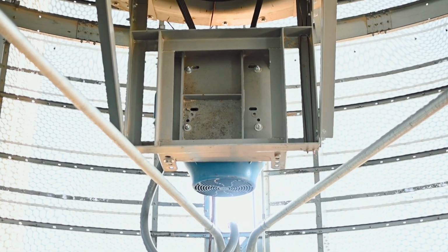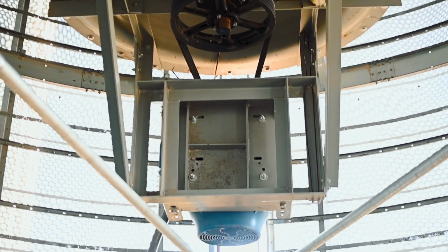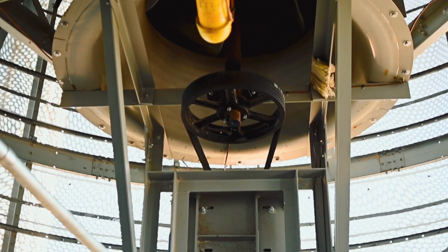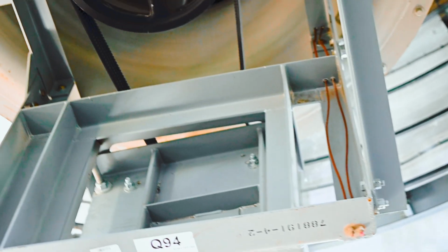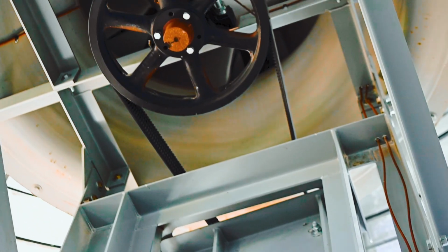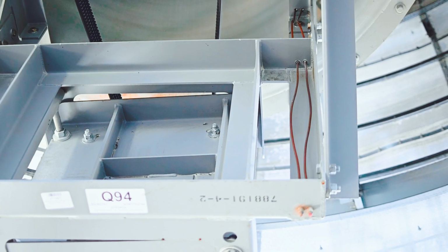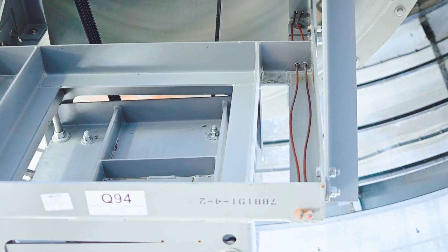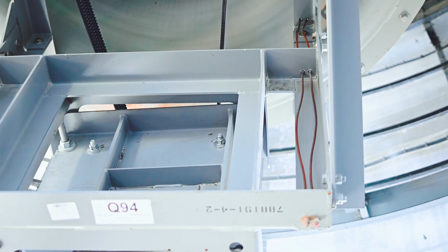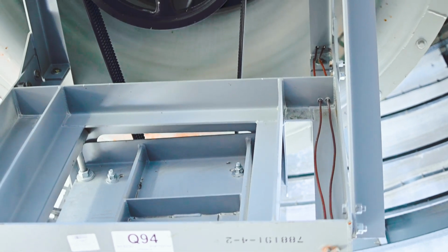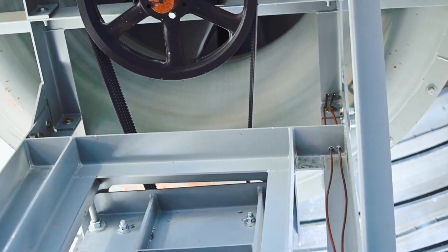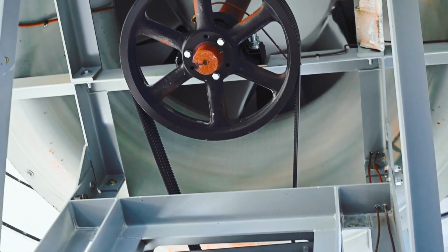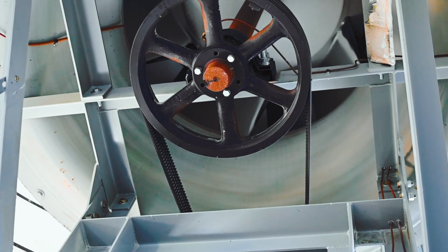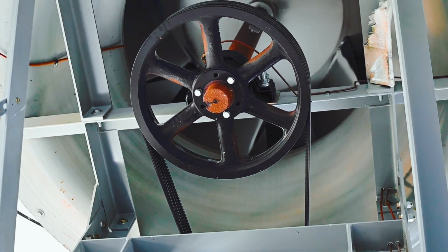So this is looking up at one of the blowers in the dryer, and you can see we need to check belt tension and adjust that yearly. Whether it's a pivoting motor mount or 4 threaded rods, it's important to make sure that the motor's pulleys are parallel to the blower pulleys. Check belt tension, there's specs for that in the manual. And there's also 2 grease zerk tube lines that should be greased for the lower and the upper bearings of the blowers themselves. The amount and type of grease is specified in the manual as well.